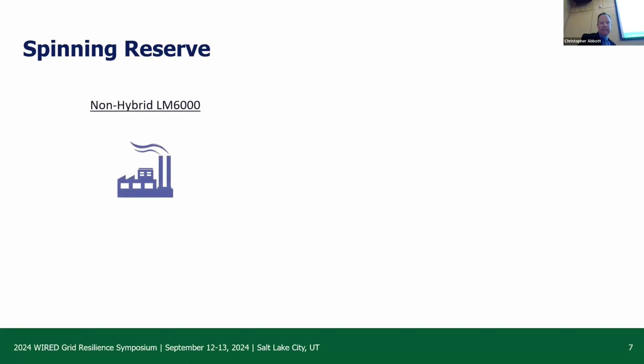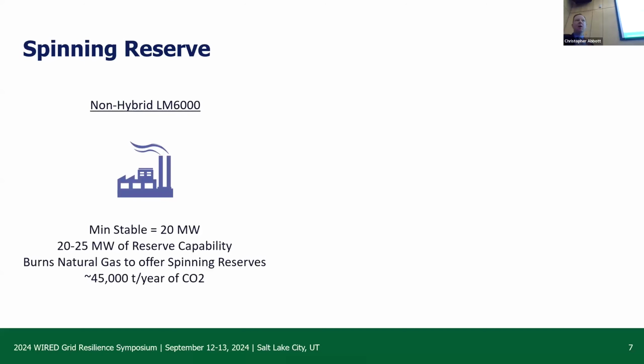So now I'd like to step through a comparison of a non-hybridized gas turbine with a hybridized gas turbine. In a slide earlier, I talked about how the nominal capacity of this gas turbine is 48 megawatts. In order to have the maximum amount of reserve capacity, we would run that gas turbine at its minimum stable generation, which is 20 megawatts. That would allow 20 to 25 megawatts of reserve capacity that we could offer to the grid. To do that, we have to burn natural gas, all right? And if we did that 24/7, 365 days a year, that would equate to 45,000 tons of CO2 being emitted.